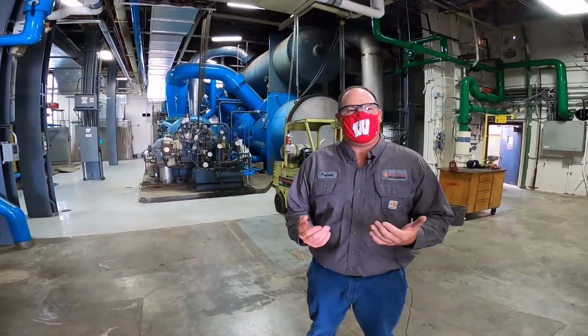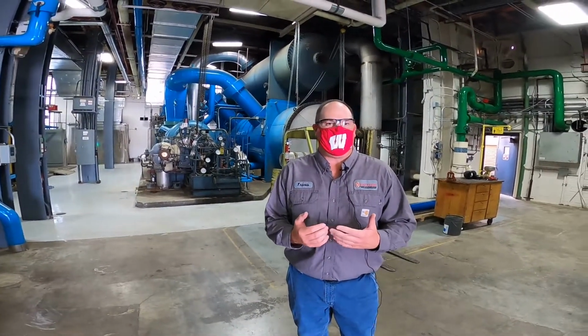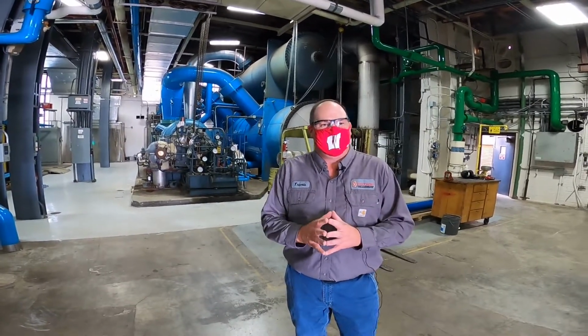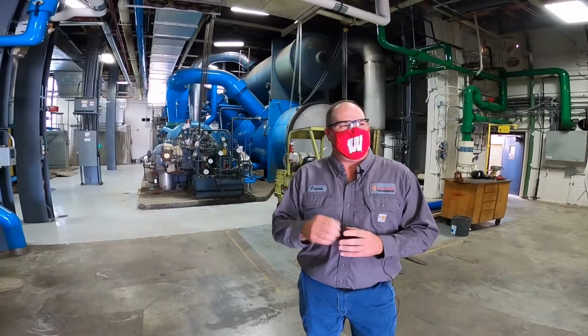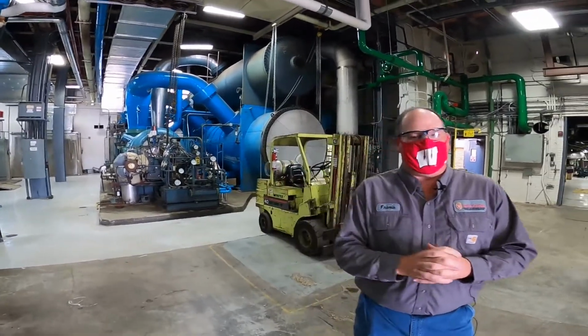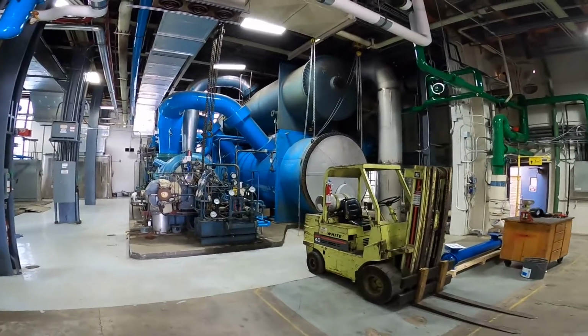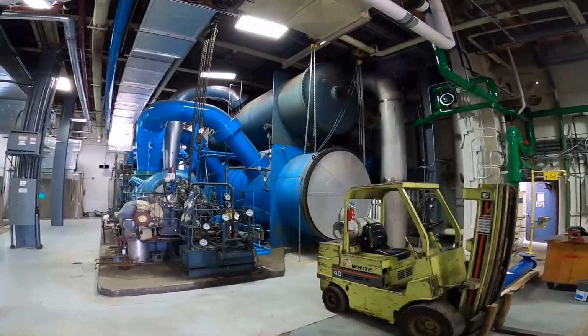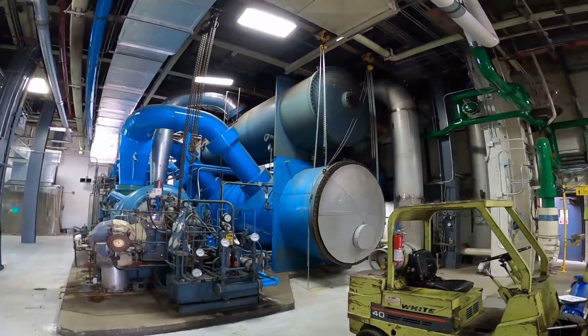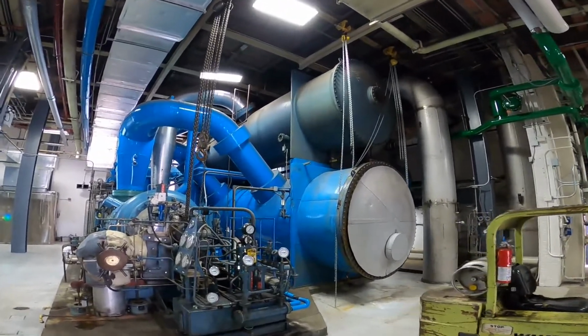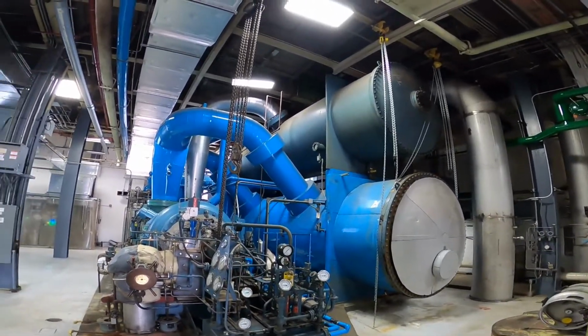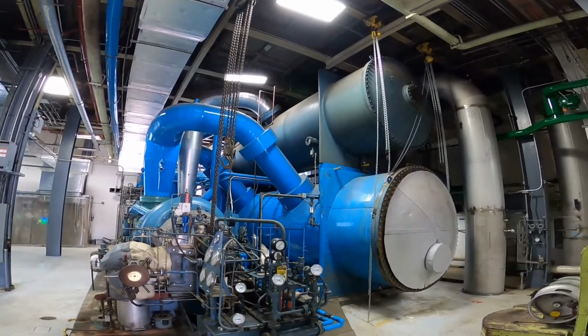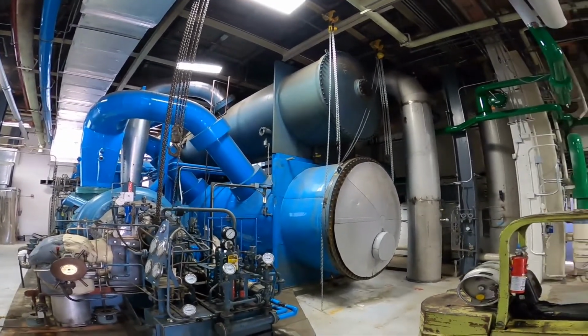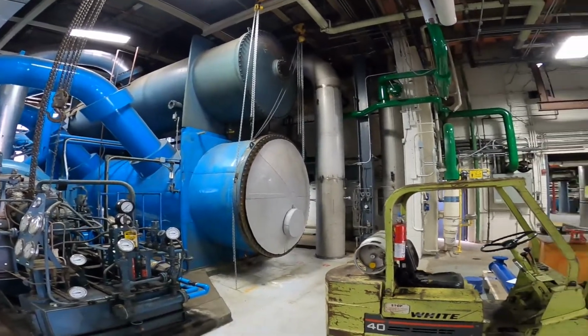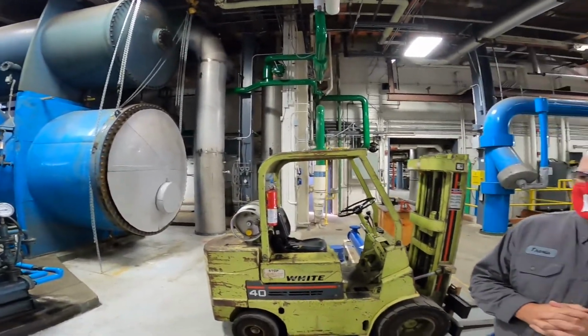All right, we're down in our chill water control area of the plant. What we have down here are 4 steam turbine driven chillers. Right behind me you can see one of the world's largest chillers produced today. You're looking at 8,000 tons of capacity. We use R22 as a refrigerant. That's what allows us to get to that capacity. If we were to switch to R134A, we would actually lose about 3,000 tons of capacity.